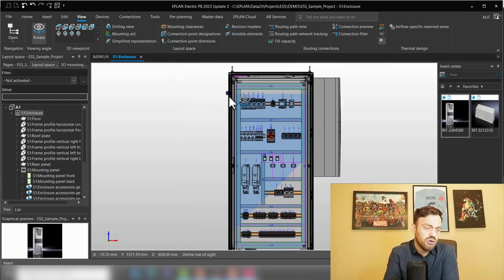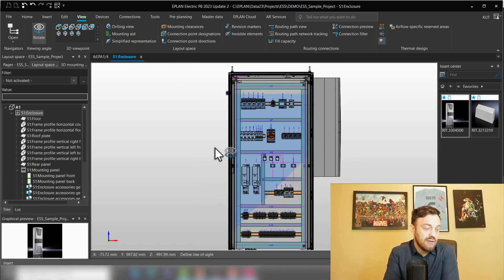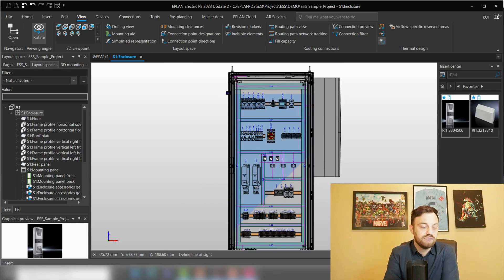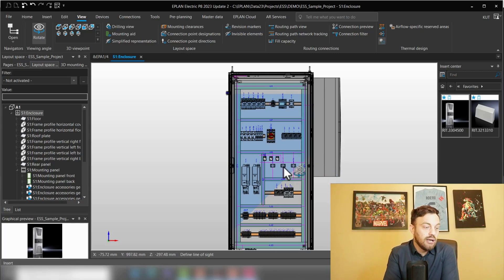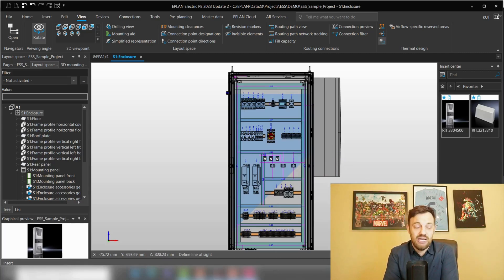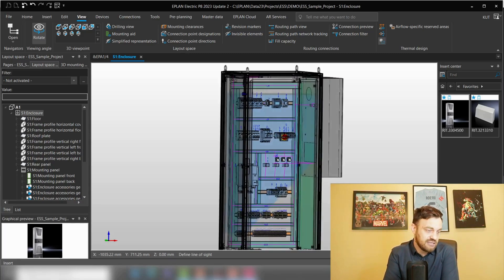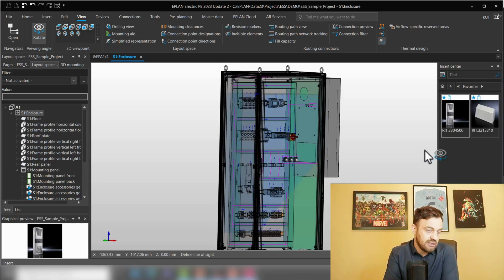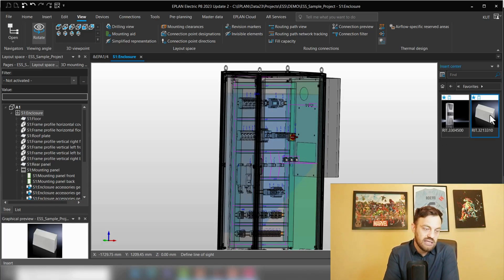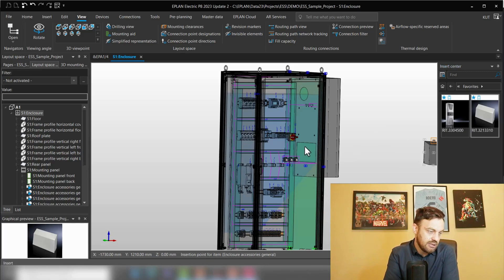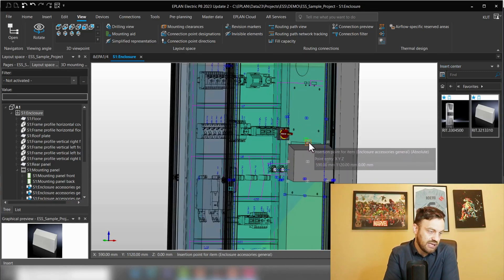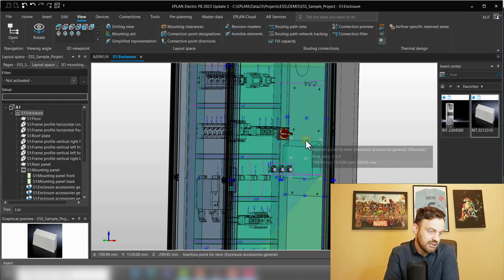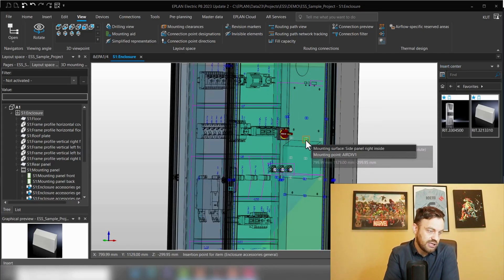There is a simple solution to climatize the whole enclosure and that will be adding some accessories like for instance this air diverter. If I select this air diverter here and place it on the mounting point here, you will see suddenly the airflow direction goes down.